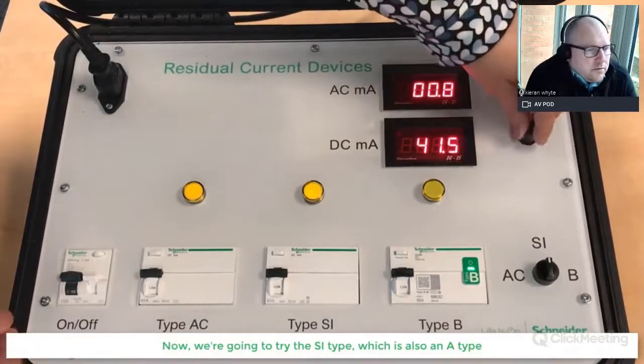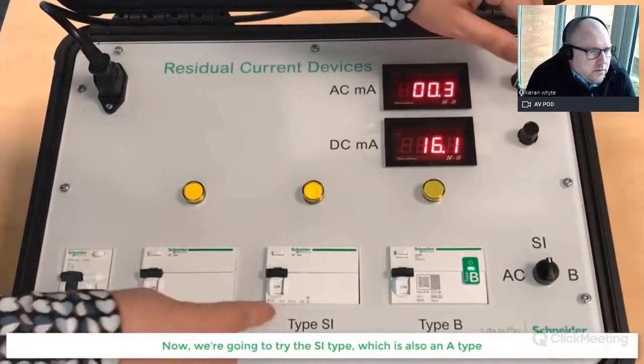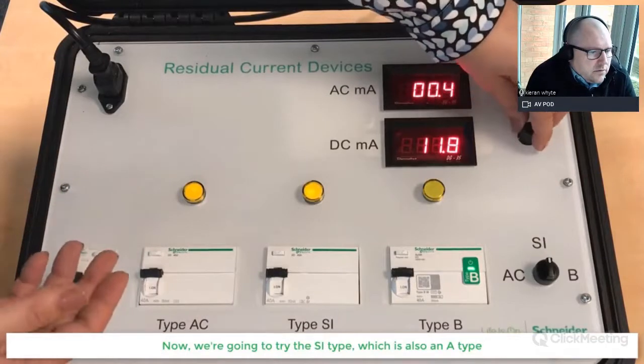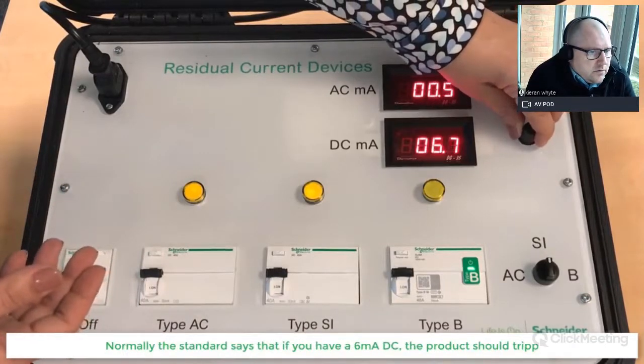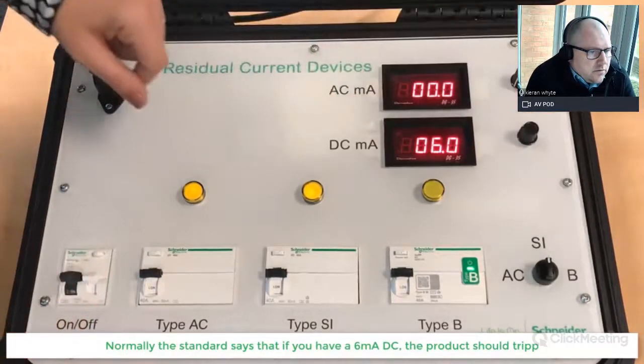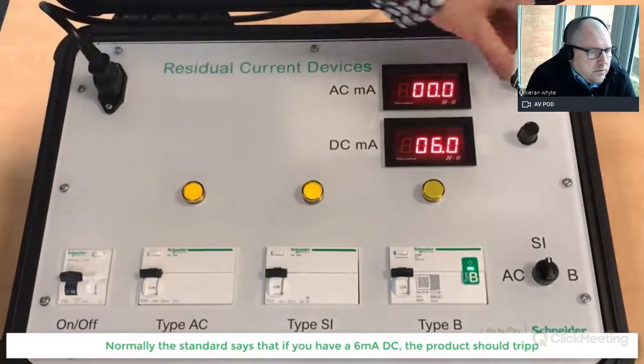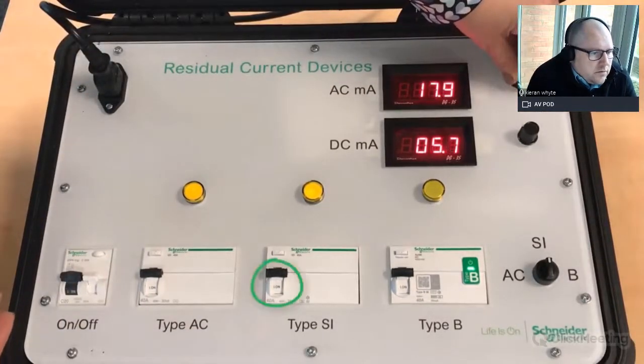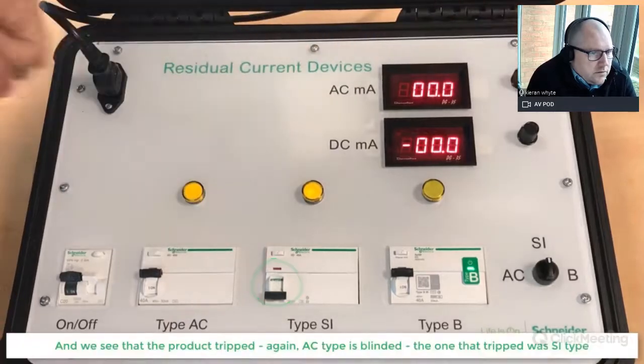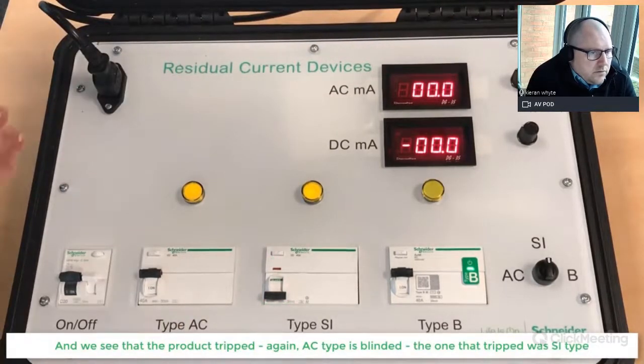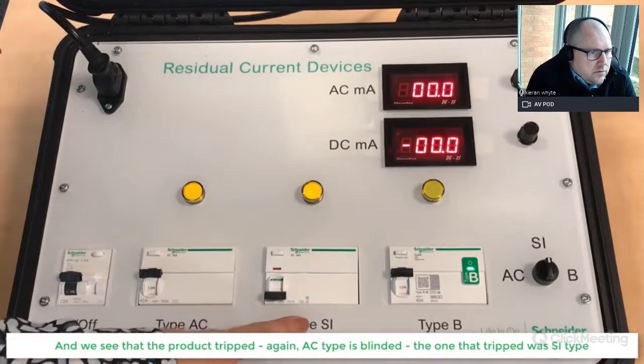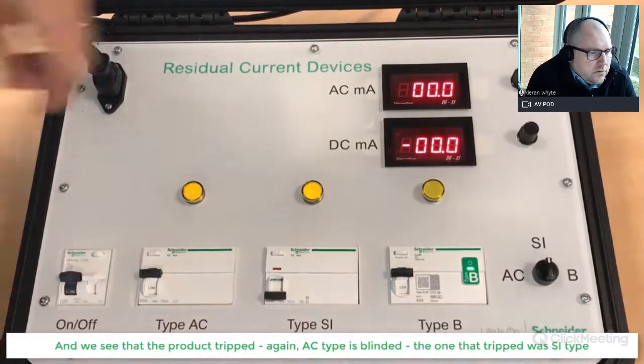Now what we're going to do is to put in the SI type, which is also an A type. Normally the standard says that if you have a 6 milliamp DC, it should trip. So we're going to start, and we see that the product trips. Again, the AC type is blinded. The one that tripped was the SI type.